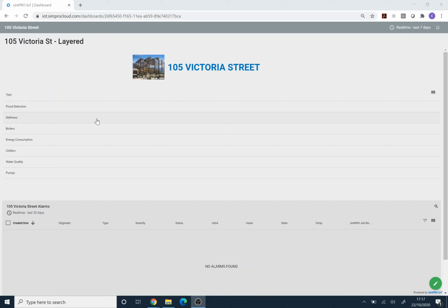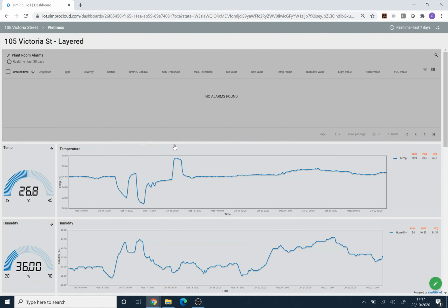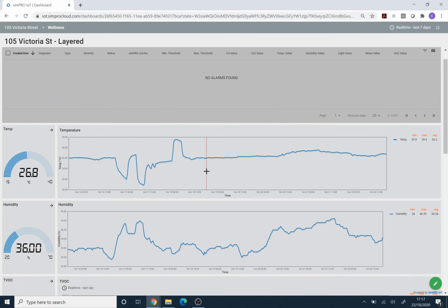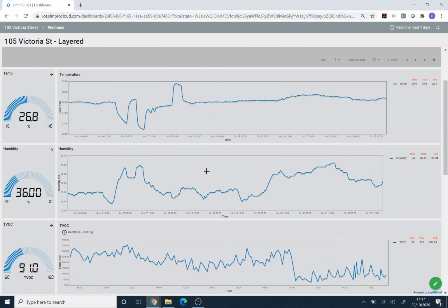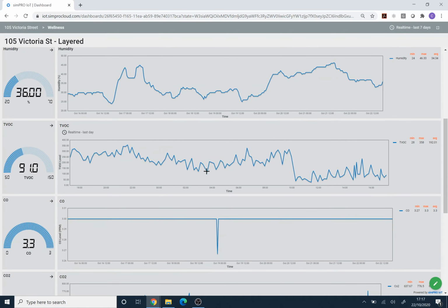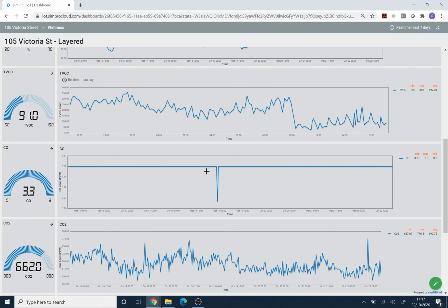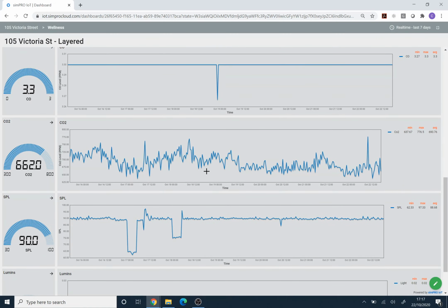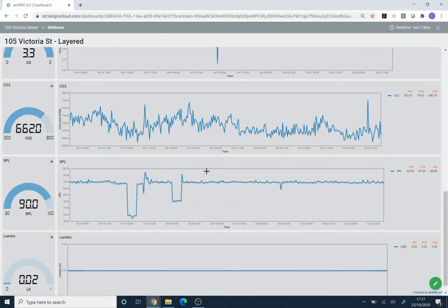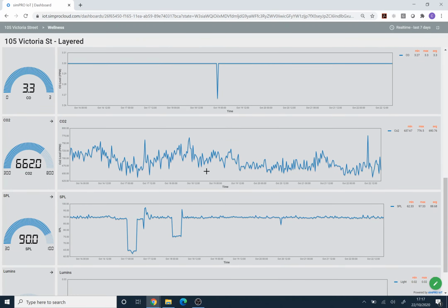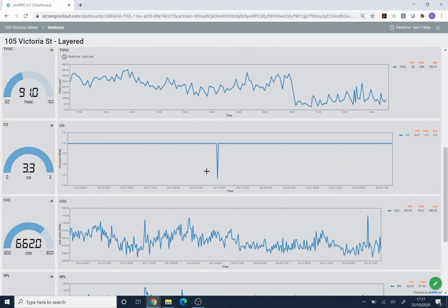Finally, we have included one of our advanced environmental systems on a free trial. This unit provides a range of measurements that aid in worker and tenant comfort, including temperature, humidity, CO, CO2, volatile organic compounds, light and noise. These metrics allow us to optimise those working conditions that can be directly impacted by HVAC plant equipment and diagnose potential issues. With the advent of COVID, there is particular interest in the measurements of VOCs and CO2 to identify possible issues with air ventilation in highly trafficked zones within a building that could indicate high-risk areas.